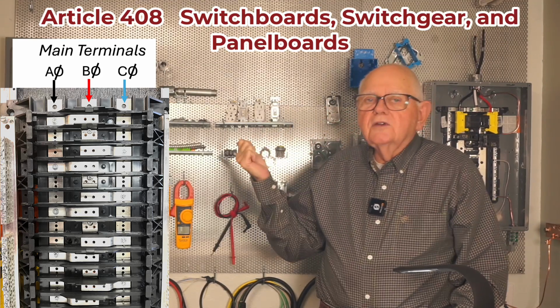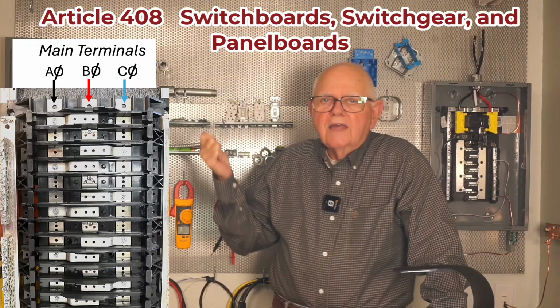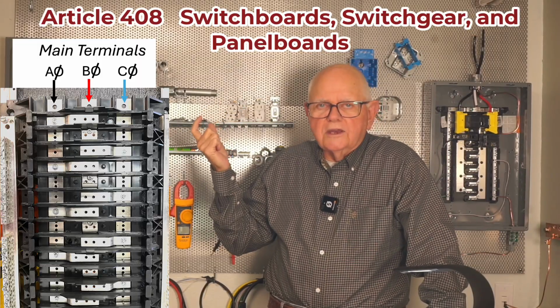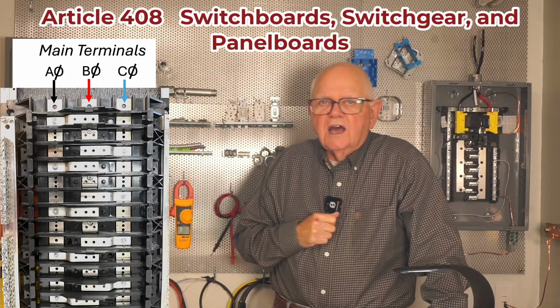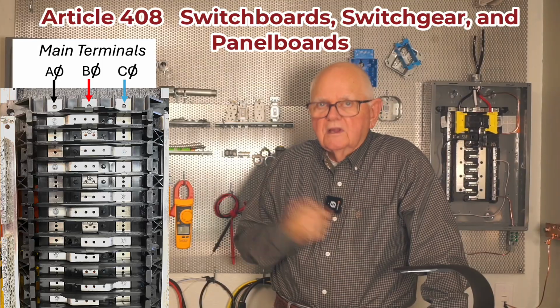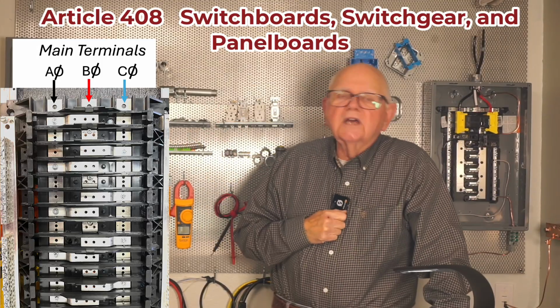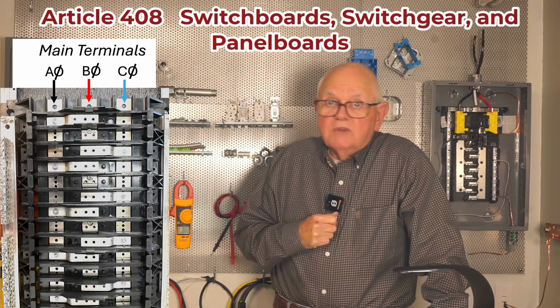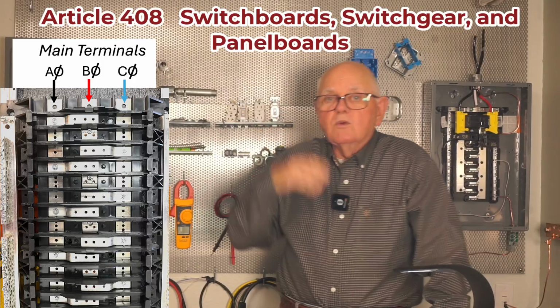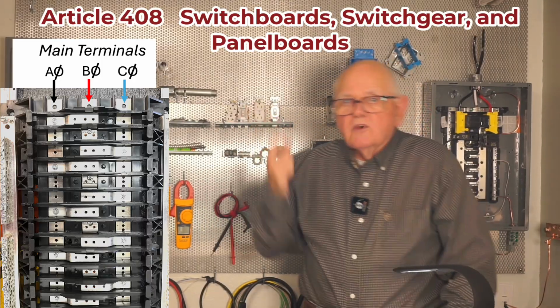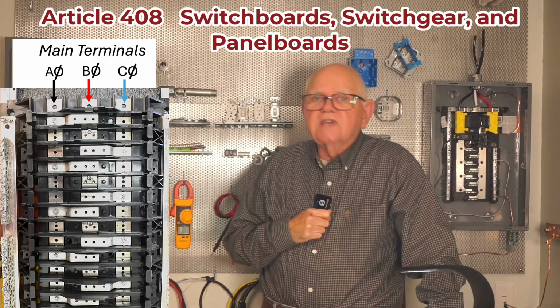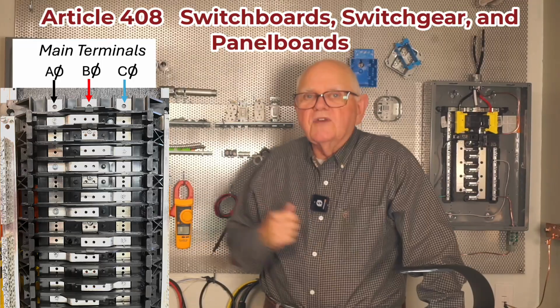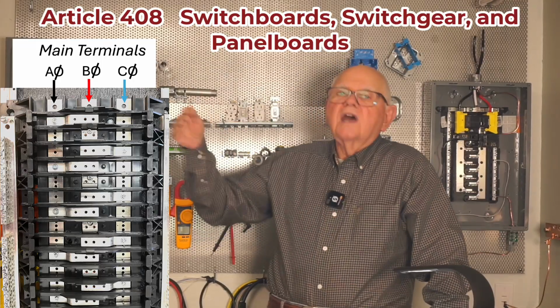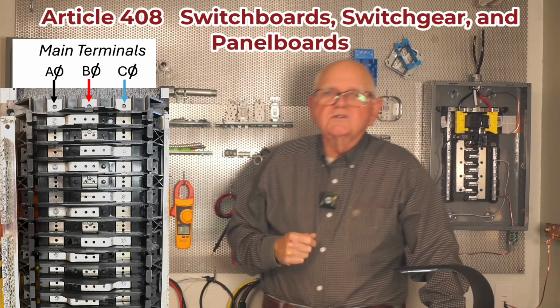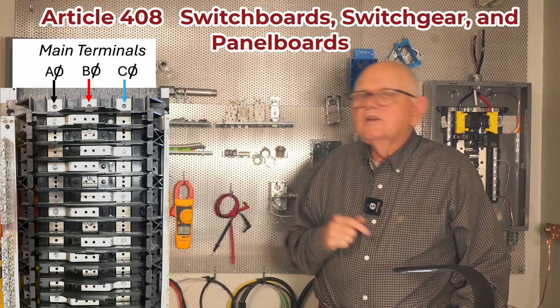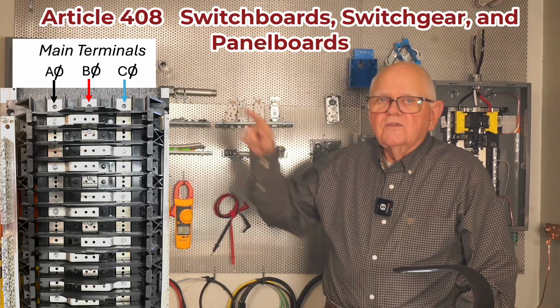Hey, while we're here, notice on that panel board, if I plug in a single pole breaker over on the upper left-hand side, that's going to come off of A phase. If I go right below it and plug in another breaker, that's just going to plug into B phase. It's the way the bus work is arranged. If I take another breaker and plug in right beneath that second one, that connects to C phase. On the left-hand side of my panel boards, and sure on the single phase as well, are going to be all of my odd-numbered circuits, 1, 3, 5, 7, 9, 11.